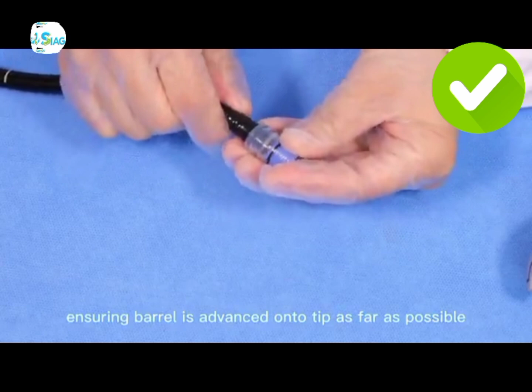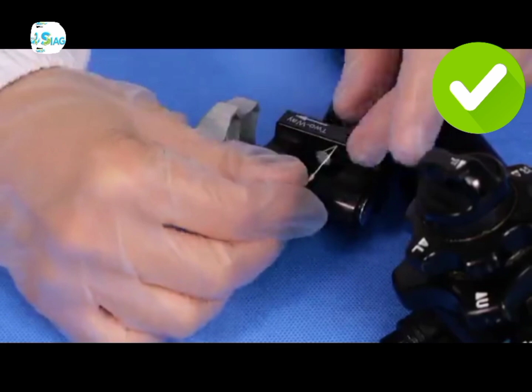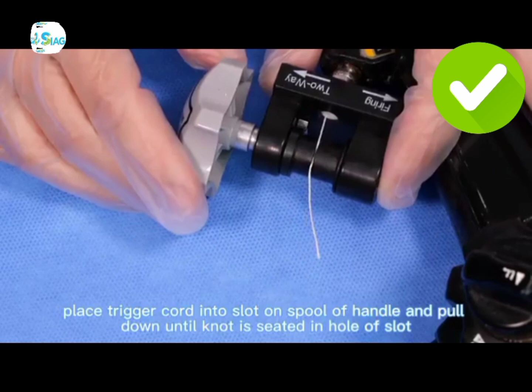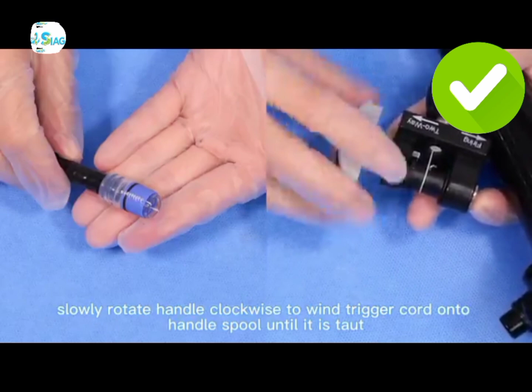Fifth, attach the barrel to the tip of the endoscope, ensuring the barrel is advanced onto the tip as far as possible. Sixth, with the endoscope tip straight, place the trigger cord into the slot on the spool of the handle and pull down until the knot is seated in the hole of the slot. Seventh, with the handle in two-way position, slowly rotate the handle clockwise to wind the trigger cord onto the handle spool until it is taut. Eighth, check the endoscopic view. To maximize visualization, the position of the trigger cord may be altered by rotating the barrel.